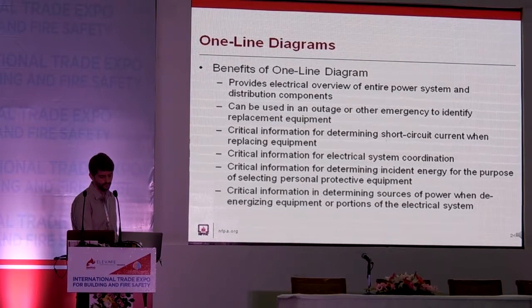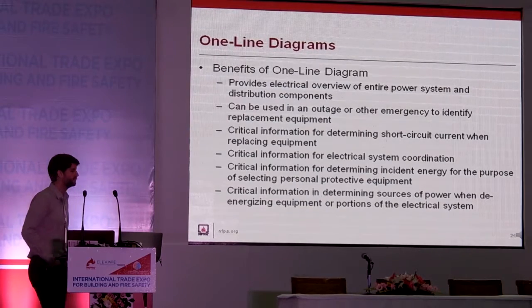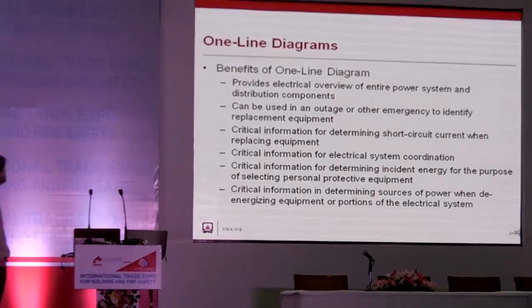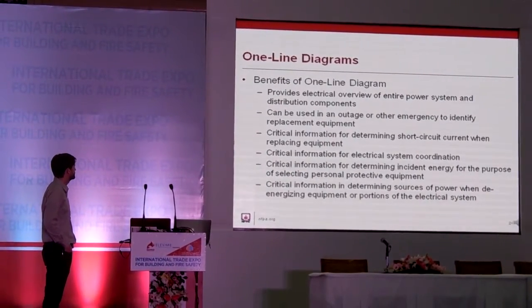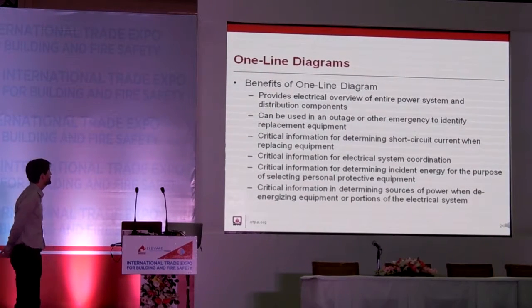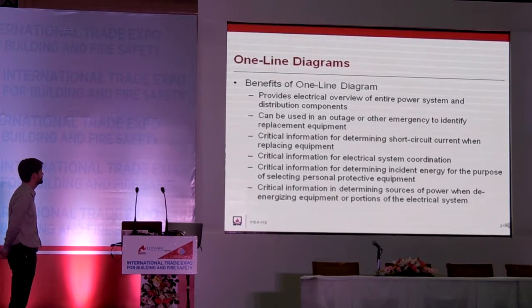A one-line diagram is an important tool that can be used by plant operators and maintenance personnel, and it can yield a lot of different pieces of information. First, the one-line diagram provides a complete picture of the electrical distribution system. It's important, of course, that it be kept up to date when there are changes made within the electrical distribution system, but an up-to-date one-line diagram does provide a comprehensive look at the electrical distribution system. The value of this information is if there's equipment failure or some other type of emergency, identifying the necessary replacement components or equipment can be ascertained through an accurate one-line diagram.